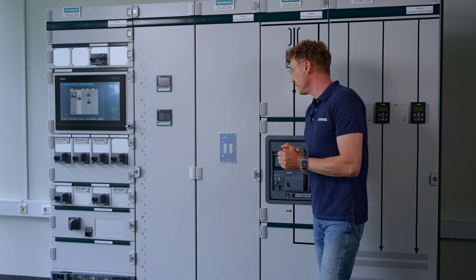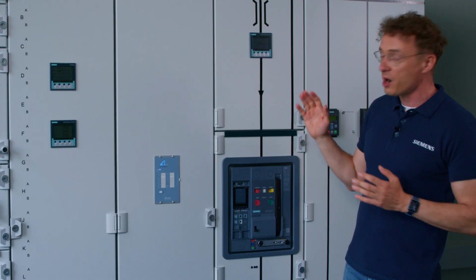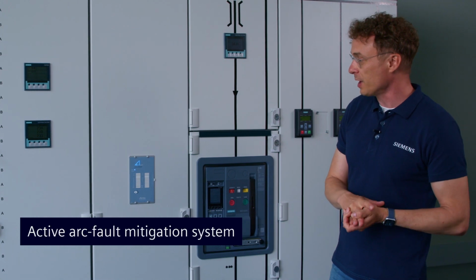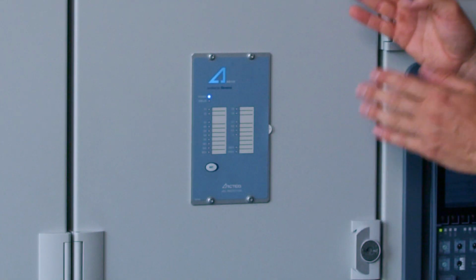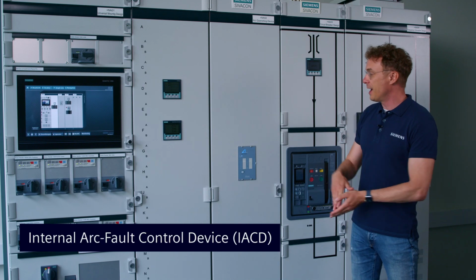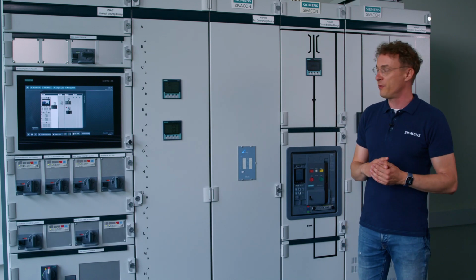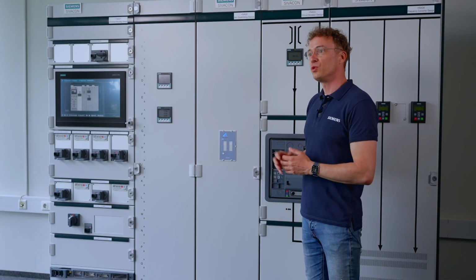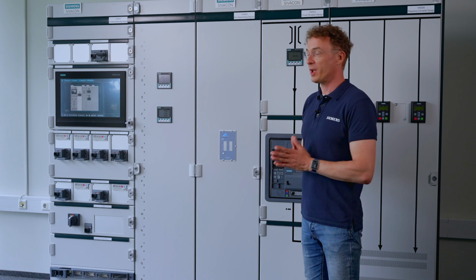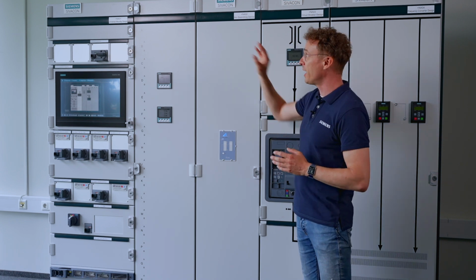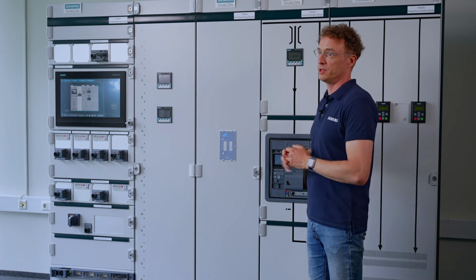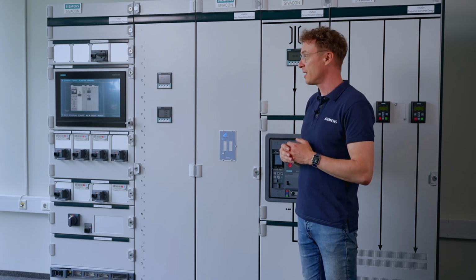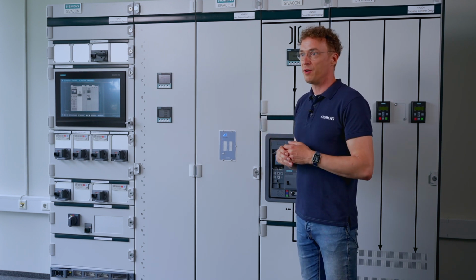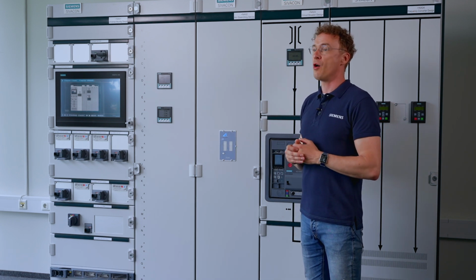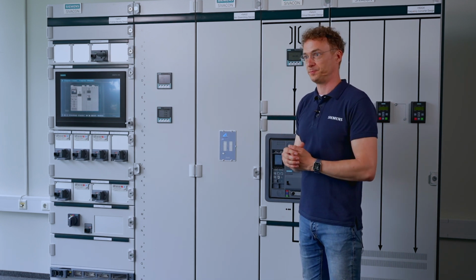Moving further to the right, we have our arc fault mitigation system consisting of the arc detection relay, and inside the cubicle we have the arc quenching device. This system is used to enhance the arc fault safety level of the switchboard. How does it work? There are light sensors installed throughout the switchboard in several locations, and these sensors monitor for the light emission of an arc fault.